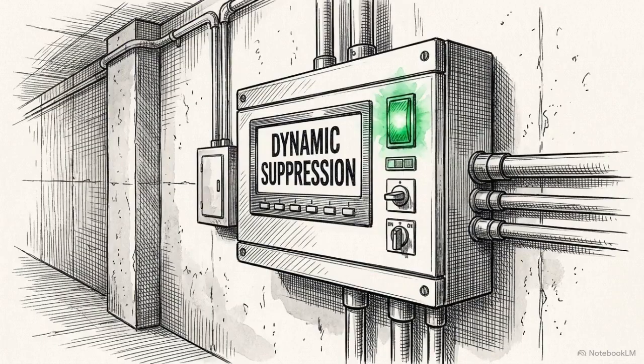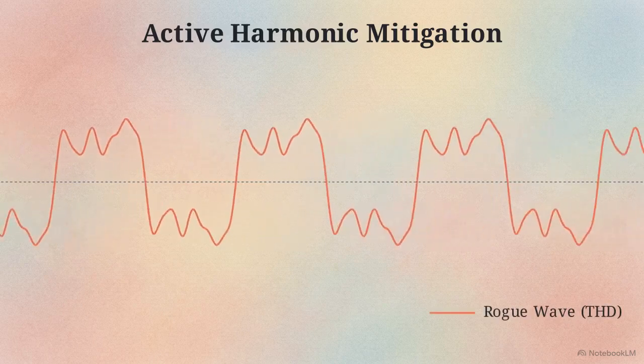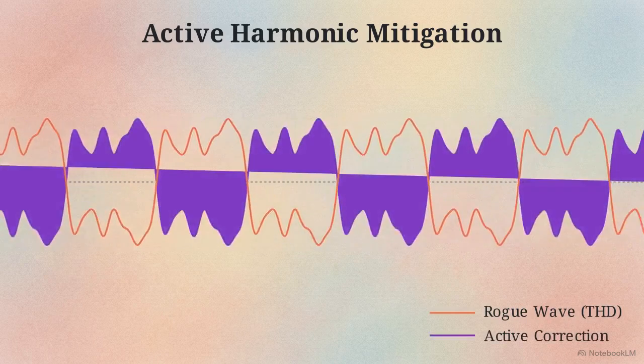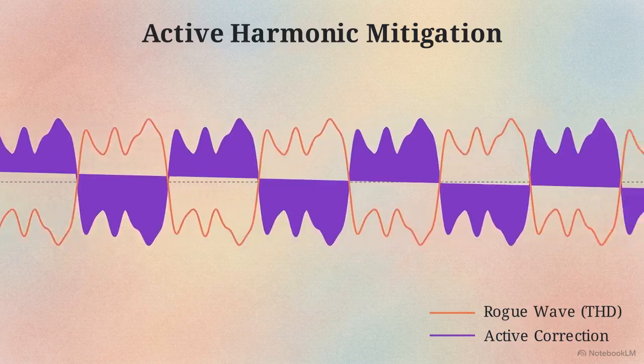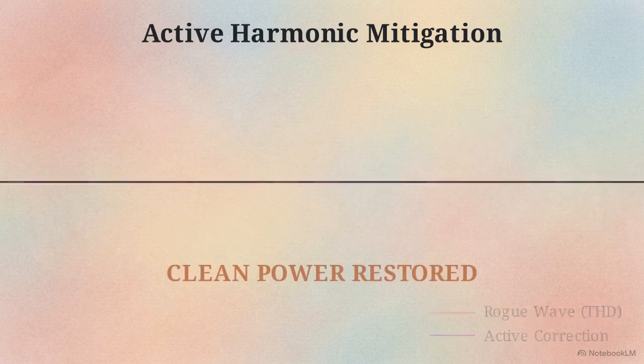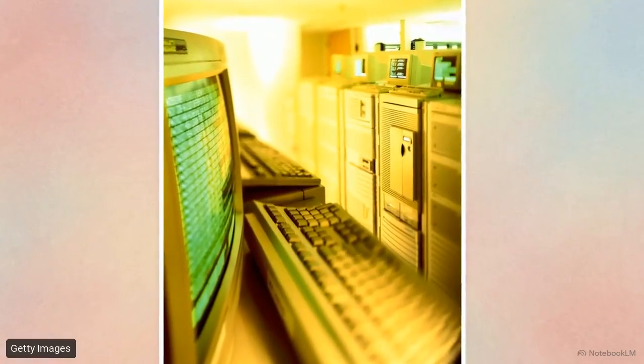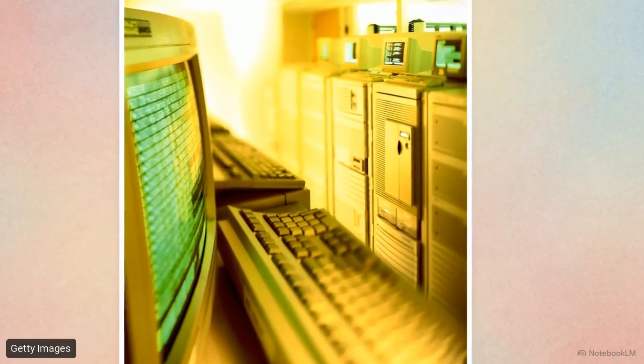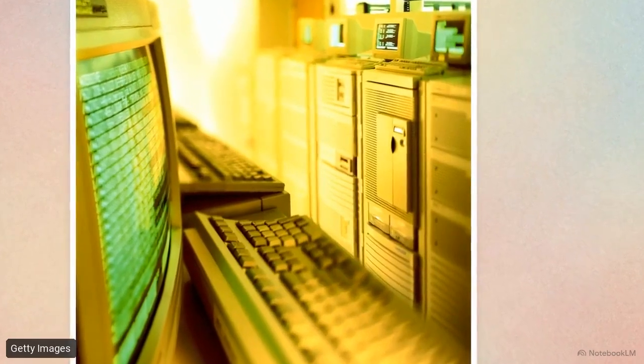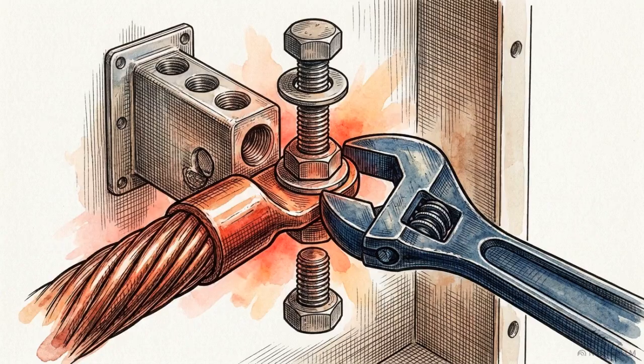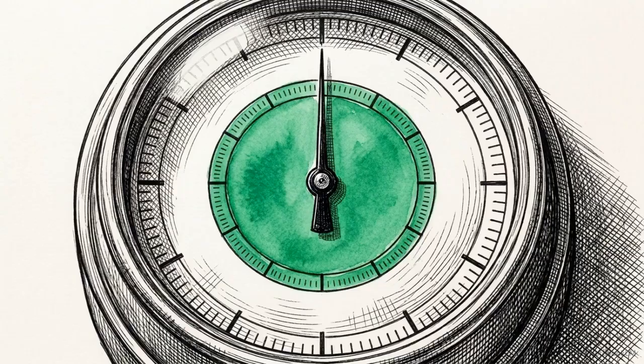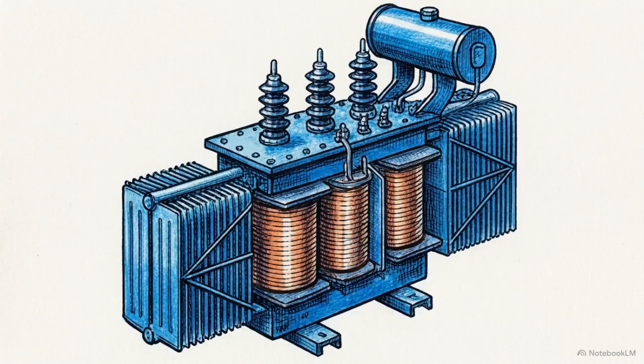For complex facilities, the standard for suppression is the active harmonic filter. This animation shows how an active filter reads the electrical distortion in real time, then instantly injects an exact inverted mirror image of the rogue wave, canceling the noise out completely. Modern electronics have established a high-frequency demand on our infrastructure that building codes are only now beginning to recognize. Triplens remain a severe architectural risk, but by deploying the right mitigation gear, we can keep the grid balanced, the hardware cool, and our buildings safe.